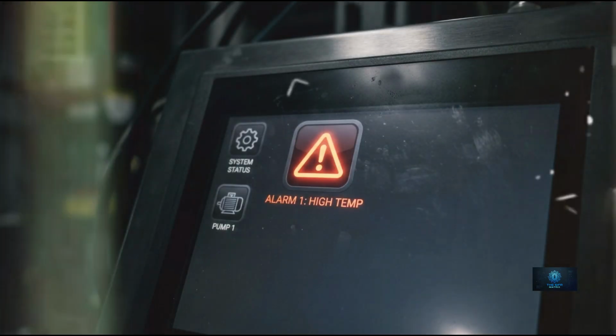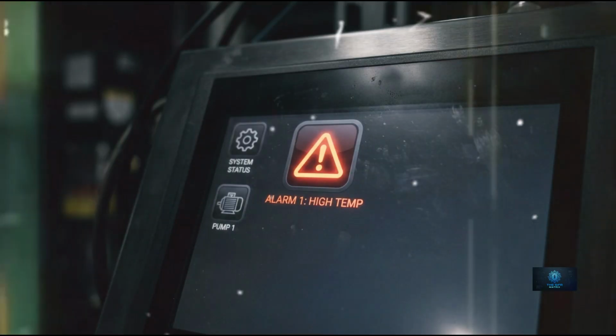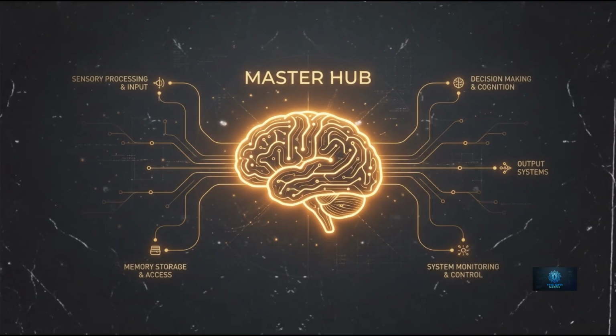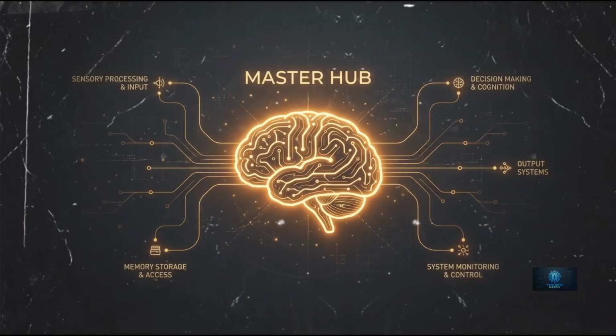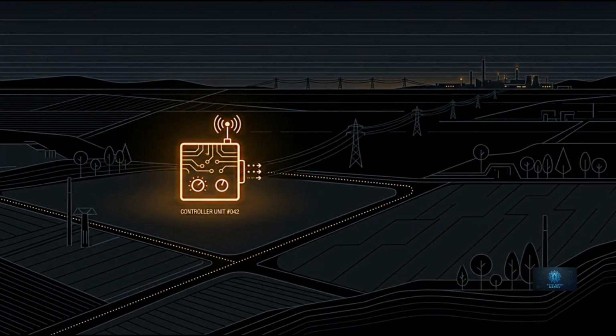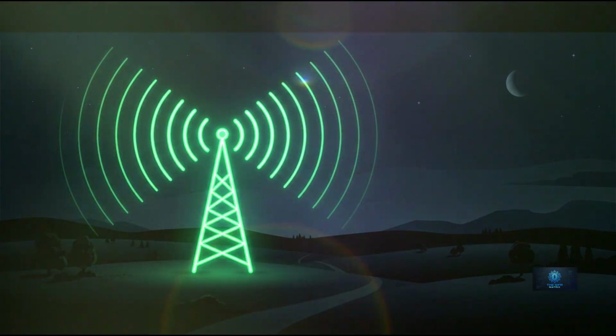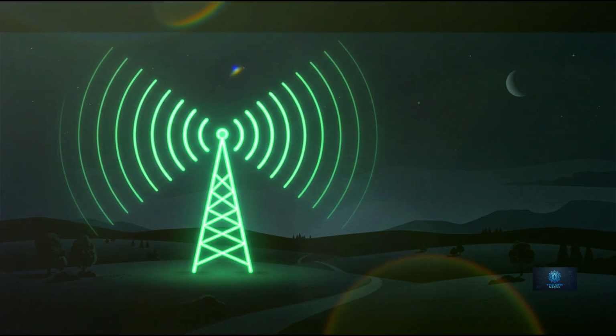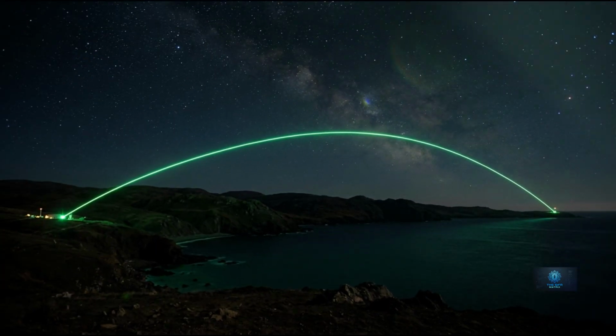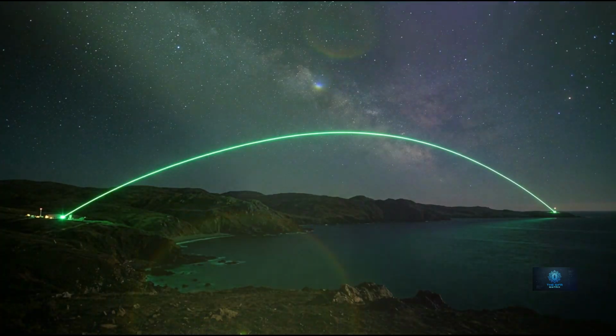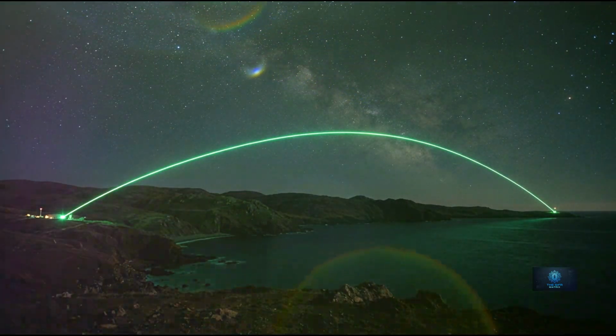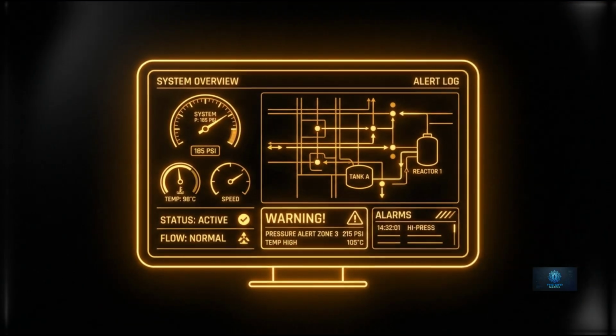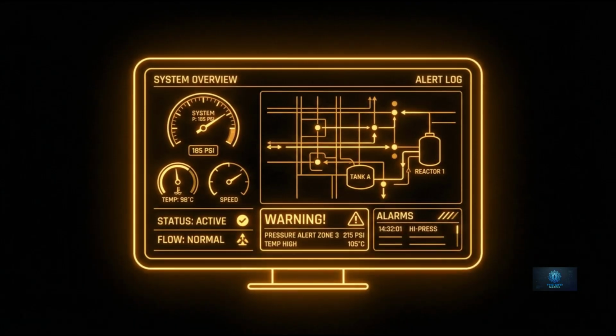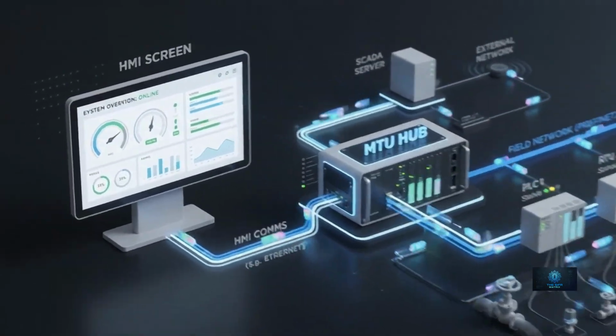A SCADA system is built from a few key pieces. At the center sits the Master Terminal Unit, or MTU, the brain, usually software running in the control room, collecting data and issuing commands. Out in the field, RTUs and PLCs, the same controllers from our last episode, gather readings and execute those commands on physical equipment. Connecting them is a communication network, sometimes radio, sometimes cellular, sometimes fiber, often stretching across huge distances. And tying it all together visually is the HMI, the human-machine interface, the actual screen an operator watches, showing the entire system as clean, readable dials, maps, and alarms instead of raw data.